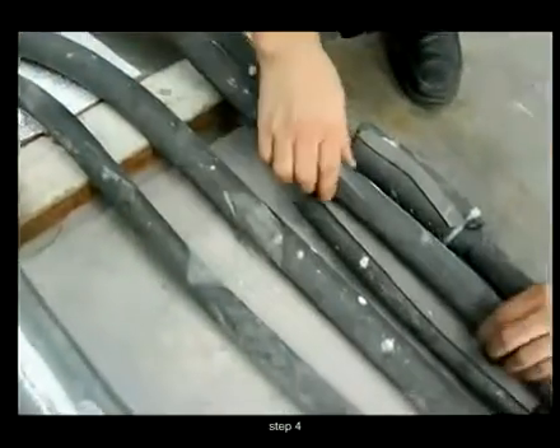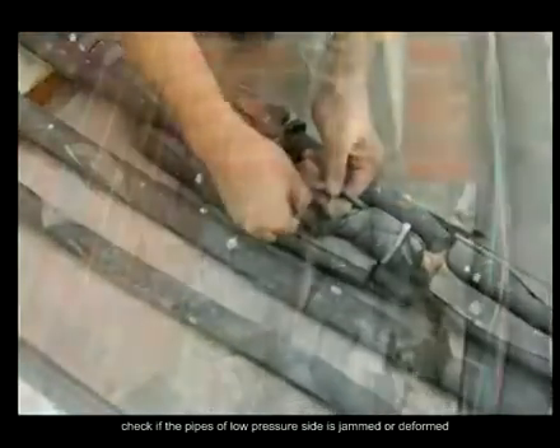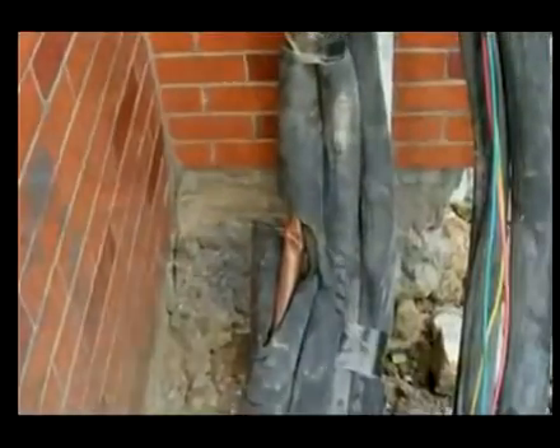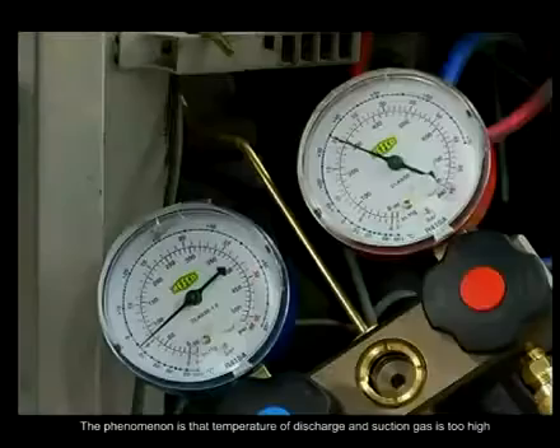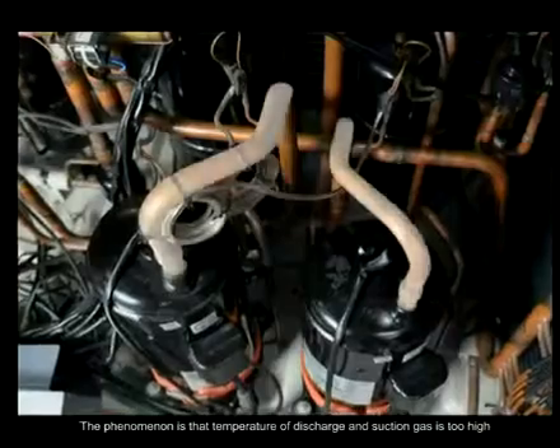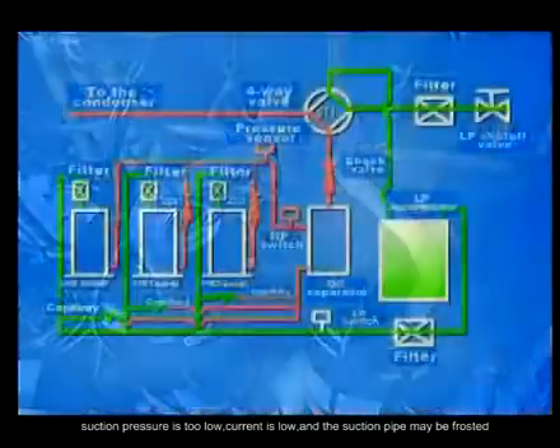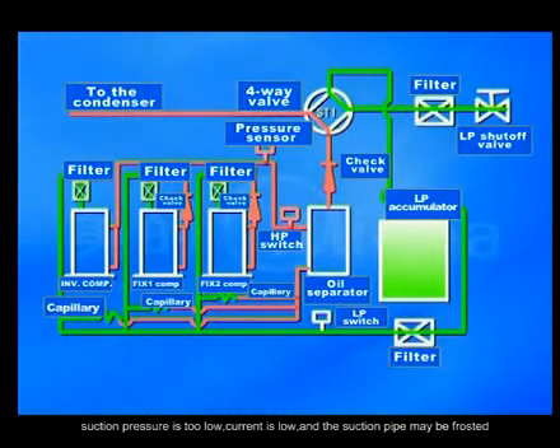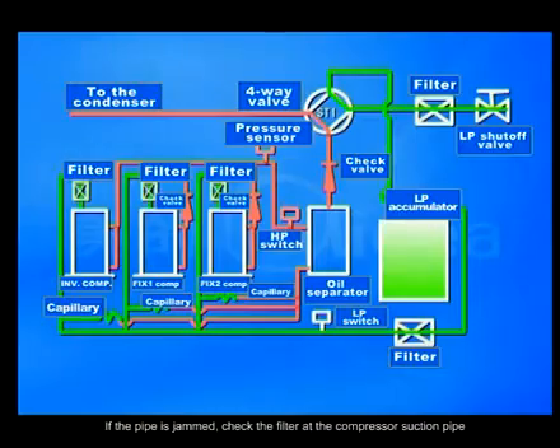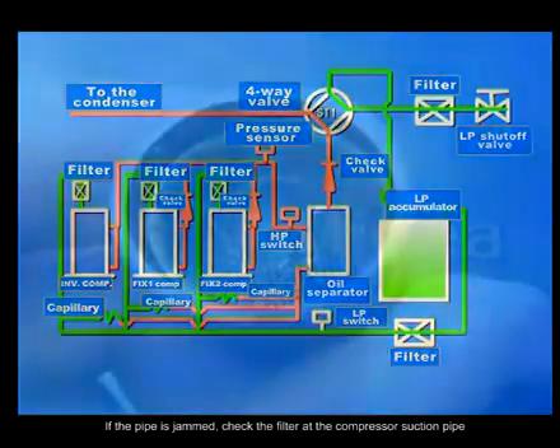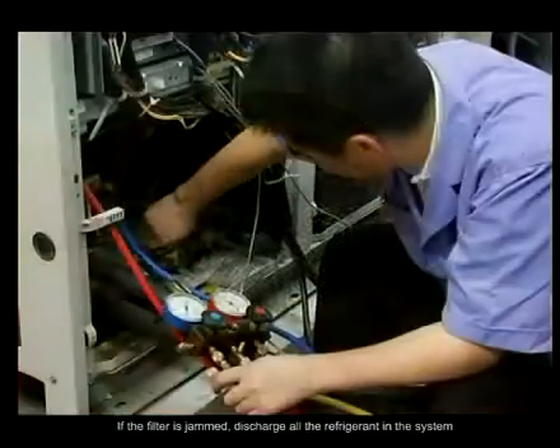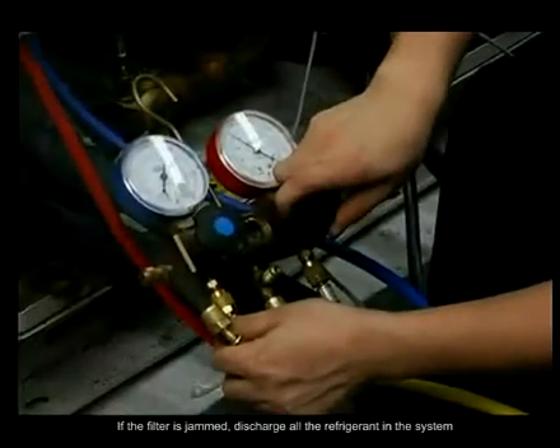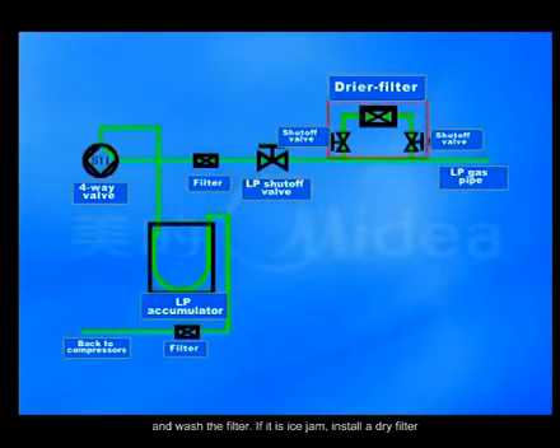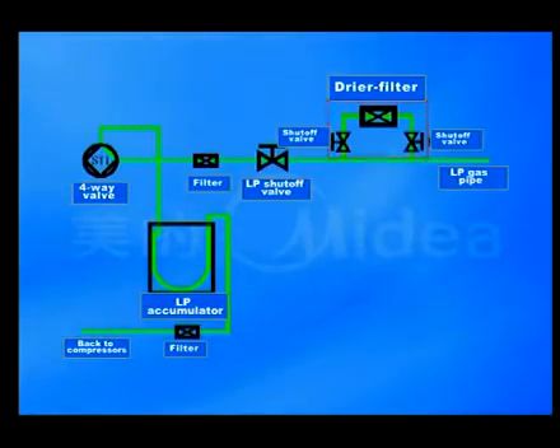Step 4. Check if the pipes of the low pressure side are jammed or deformed. The phenomenon is that the discharge temperature and suction gas temperature are too high, suction pressure is too low, current is low, and the suction pipe may be frosted. If the pipe is jammed, check the filter at the compressor suction pipe. If the filter is jammed, discharge all the refrigerant in the system and wash the filter. If it is an ice jam, install a dry filter. If it is normal, please go to the next step.